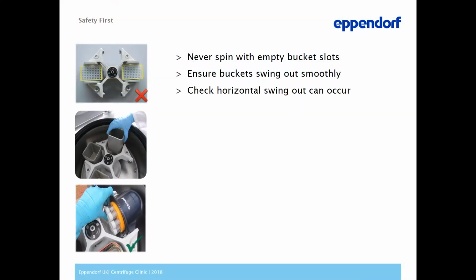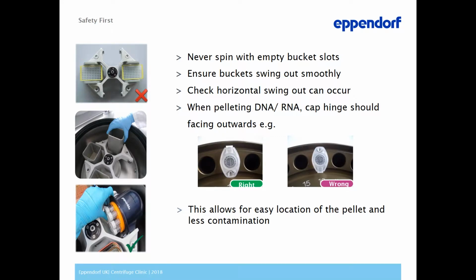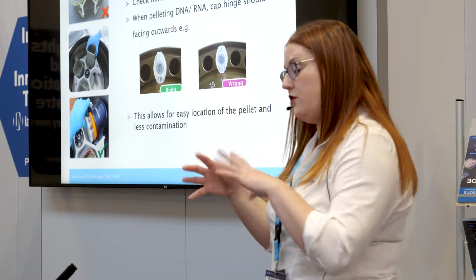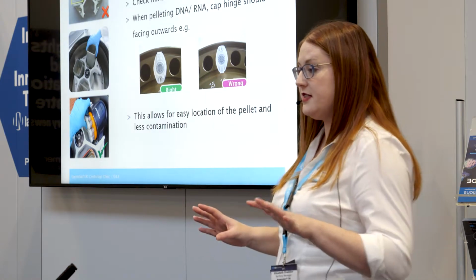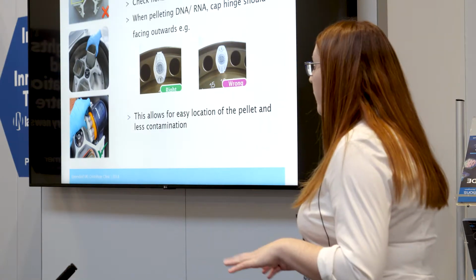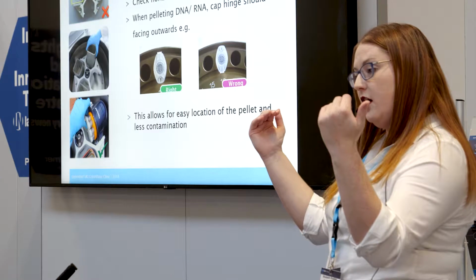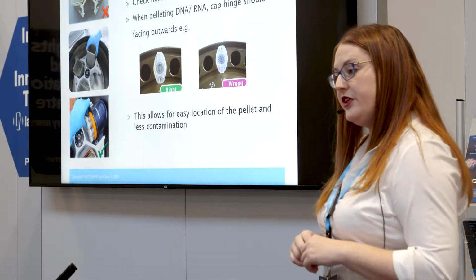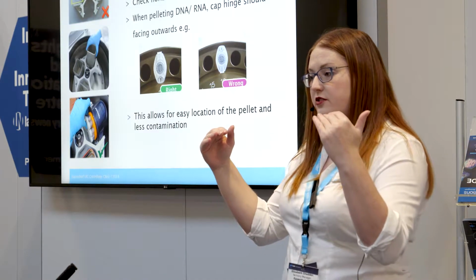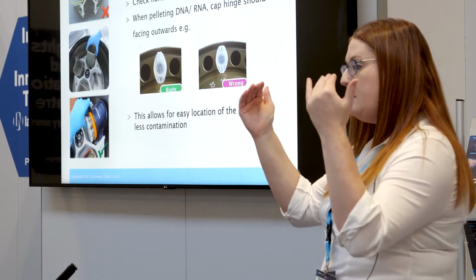So, never spin with empty bucket slots, even if it looks balanced. Because again, that will give you torsional twist on your centrifuge rotor, on the cross arms of the rotor, and it will damage it over time. Always make sure that they can swing up fully horizontal. That was the problem on the previous slide. Yes, they could go fully horizontal, but they probably wouldn't because of all the weight being at the top of the bucket.